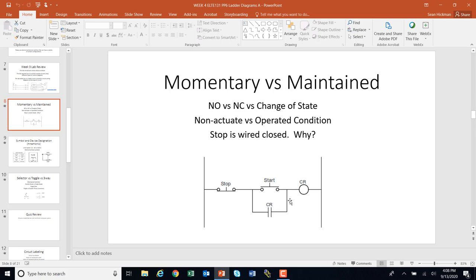So why is stop wired normally closed? If we hit start, we have our memory — let go, the control relay holds. The stop button is going to stop this. If a fork truck came along and ran over the stop button, it would be destroyed and that would cause it to open. Because it's wired closed, if something happens it opens the circuit and the control relay goes off. That's opposite from a start button, which is normally open — if a fork truck destroyed it, it would be the same open condition as when it's not actuated. So stop is looking for the condition that opens the circuit, and start is looking for the condition that closes it. Stop is wired normally closed for safety.